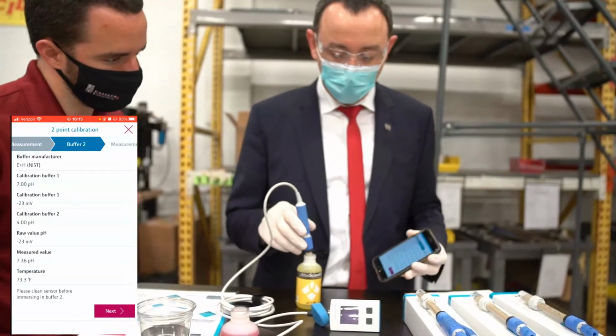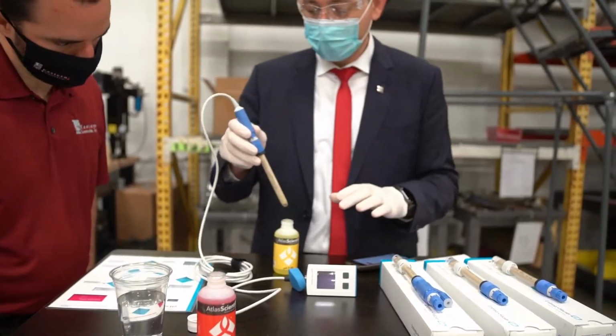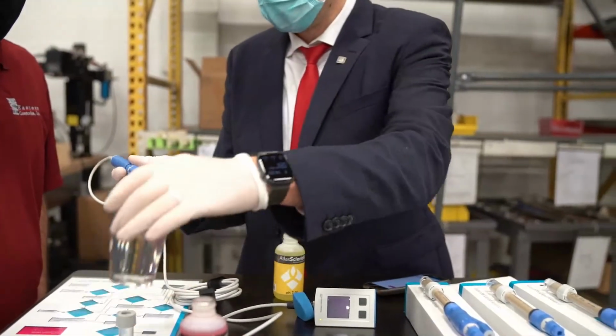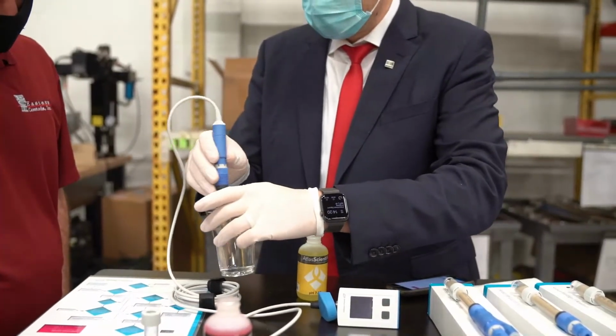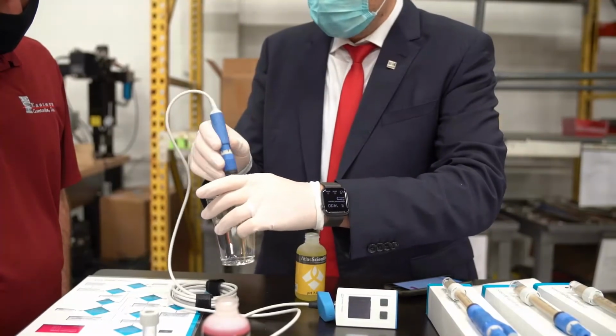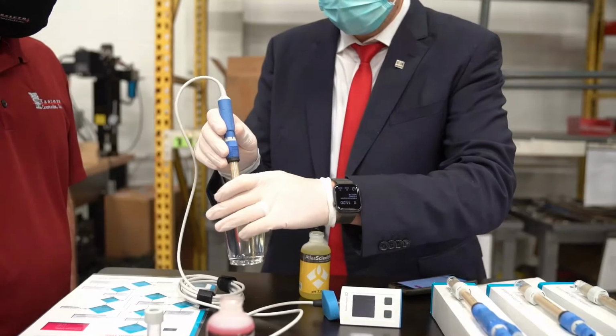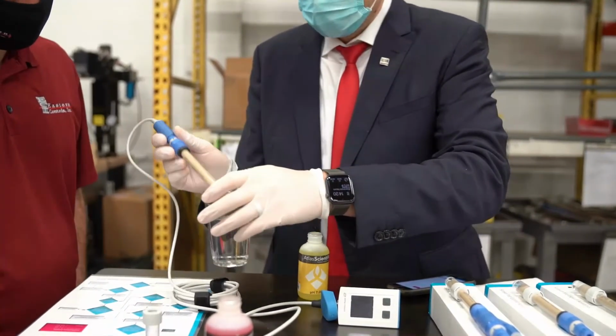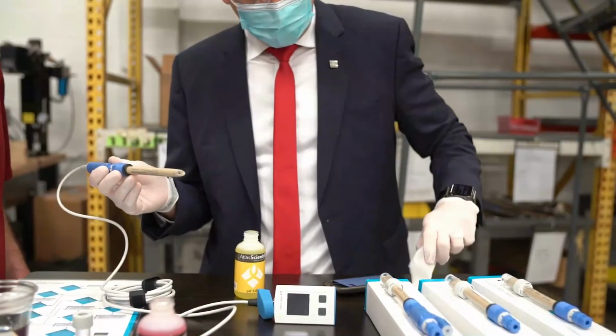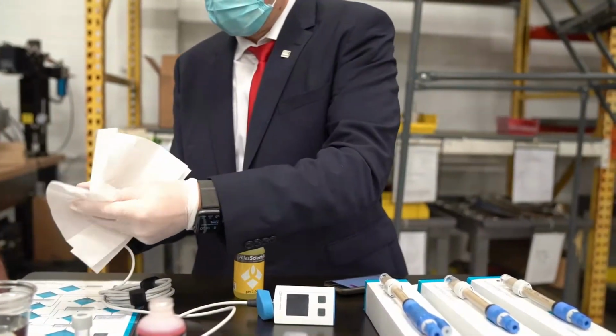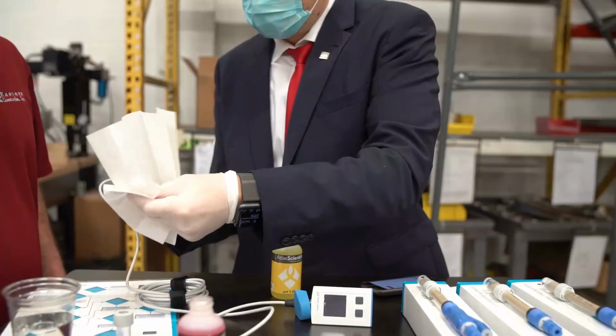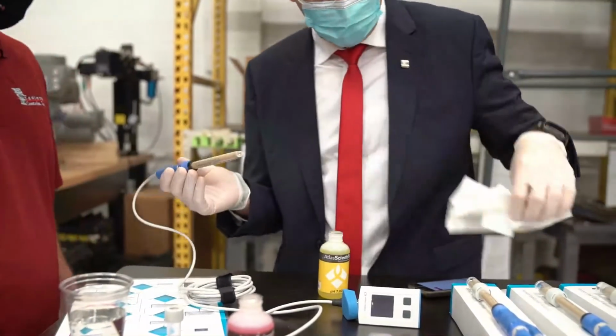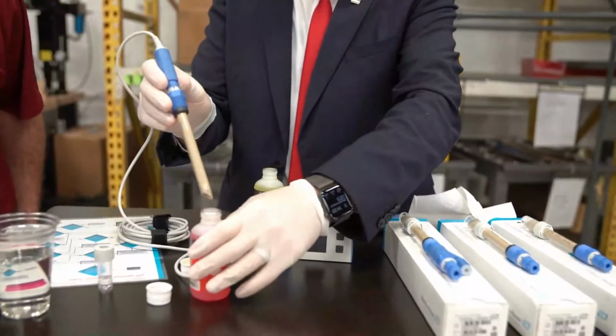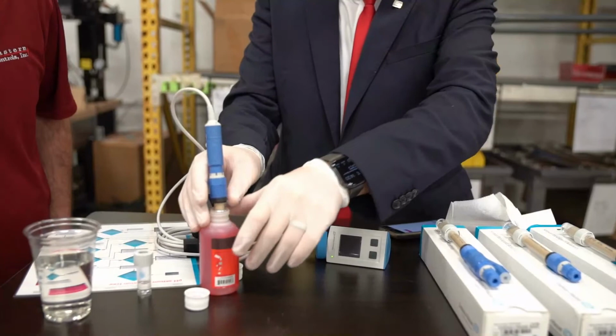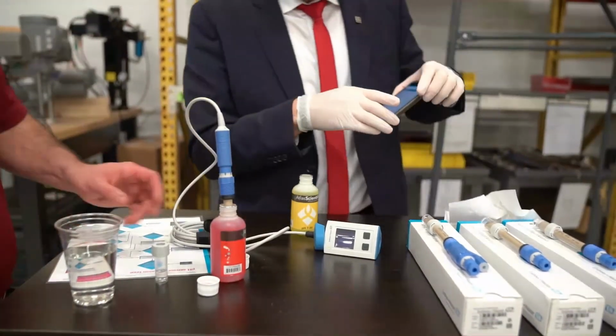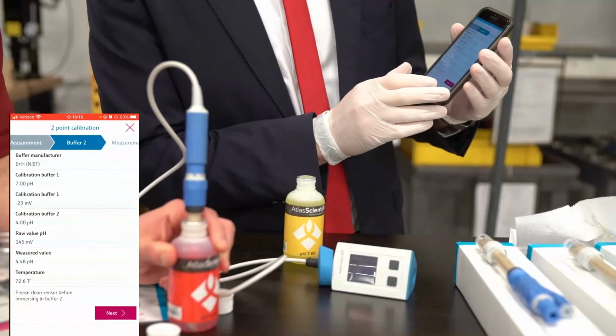Then we take the probe out of buffer 7 and clean it either with DI water or just clean water, so as not to poison the pH buffer 4. I can use the clean soft tissue to dry it out, and now I can dip it in pH buffer 4. All right, that's the 4 now. I'll hold that for you. Thank you.